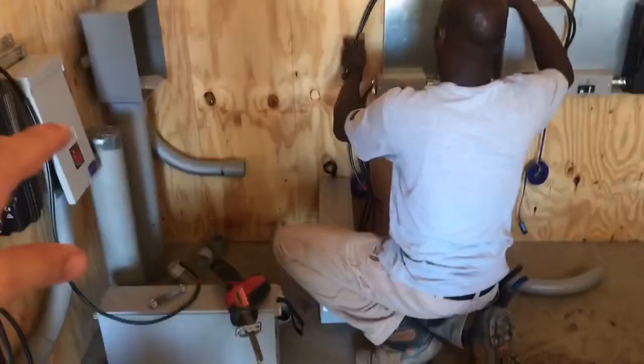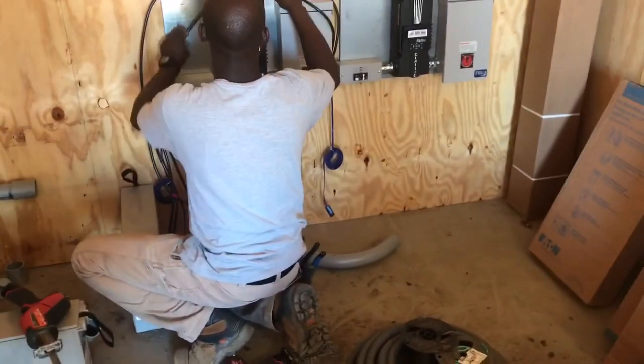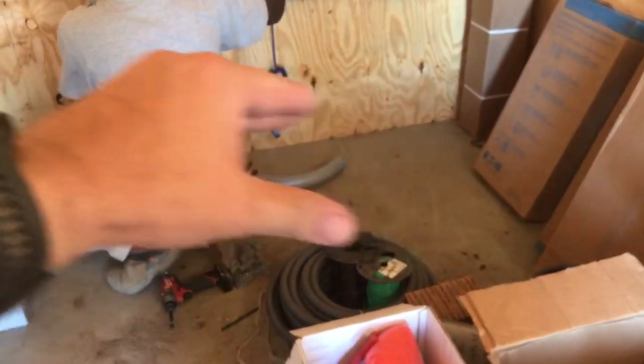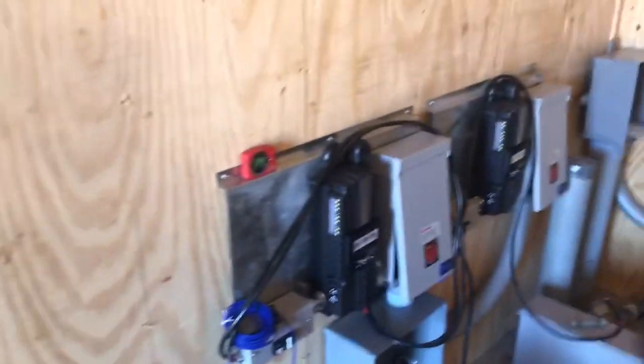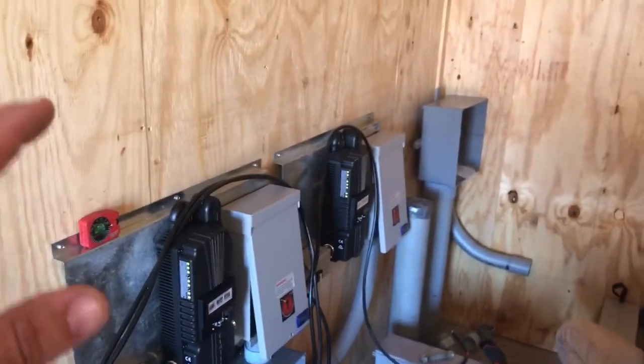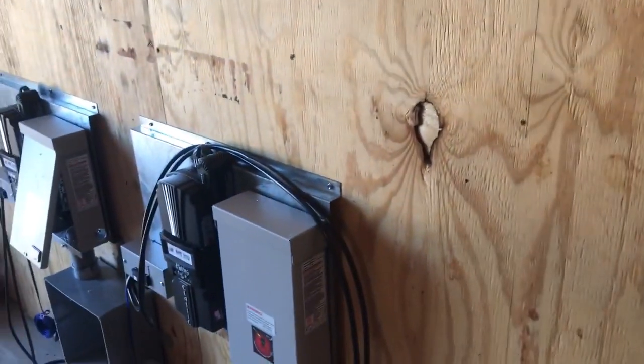I'm going to help him tie this conduit in just a second, but we're going to build a frame and set the batteries here in an L. The Connex units will go right here, then we'll take conduit on a straight run out to that service panel, from the conduit run boxes on the bottom of the inverters out to that service, so it's a very clean setup and out of the way.